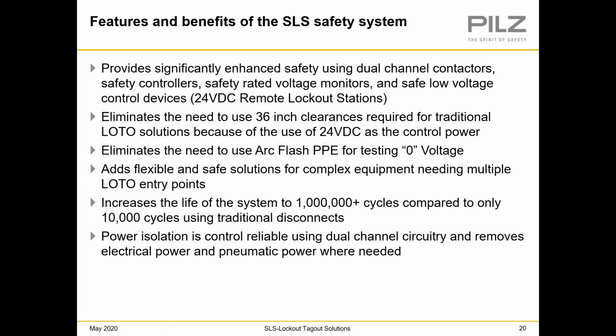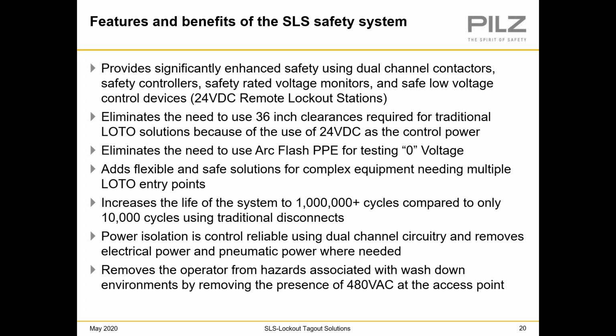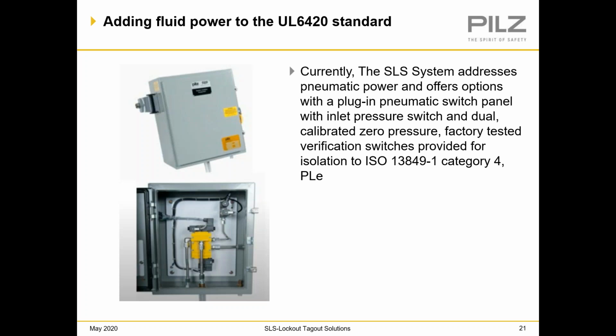And the power isolation is control reliable using dual channel circuitry, and it removes electrical power and pneumatic power where needed. And it removes the operator from hazards associated with washdown environments by removing the presence of 480 three-phase at the access point. And it has options for dealing with pneumatic pressure monitoring. And this is the add-on control cabinet for pneumatic monitoring. Currently, the SLS system addresses pneumatic power and offers options with a plug-in pneumatic switch panel with inlet pressure switch and dual, calibrated zero pressure, factory tested verification switches provided for isolation to the ISO 13849-1 standard, category 4, performance level E.